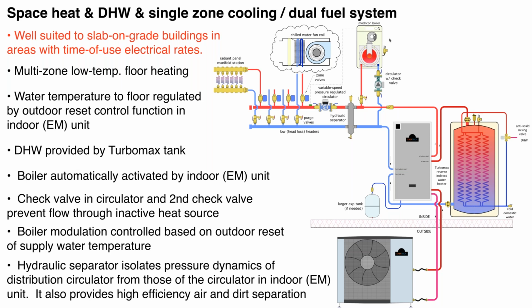One word of caution when you do that: if you're tying in any type of a conventional boiler, and by that term conventional, I mean a boiler that was not designed to operate with sustained flue gas condensation, and you're going to a low temperature distribution system, radiant panels or low temperature heat emitters of any sort, it's really important to protect that conventional boiler against flue gas condensation. We have seen situations where conventional boilers have been destroyed when a hydronic system was converted from its original high temperature heat emitters into a low temperature system.